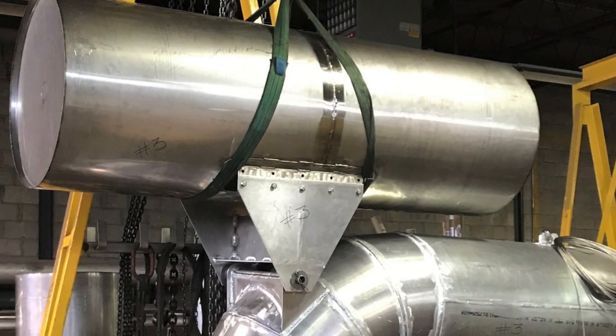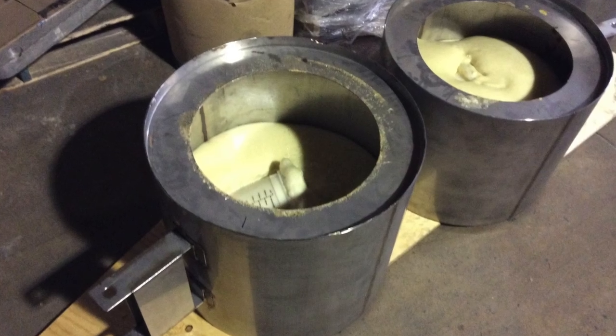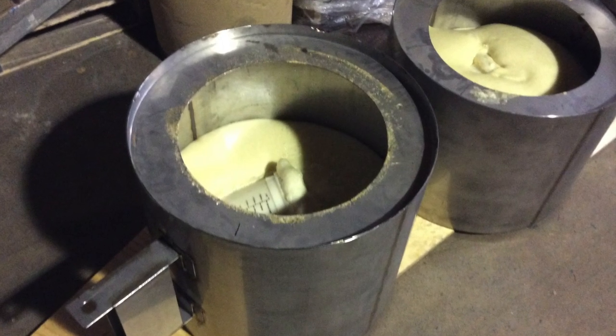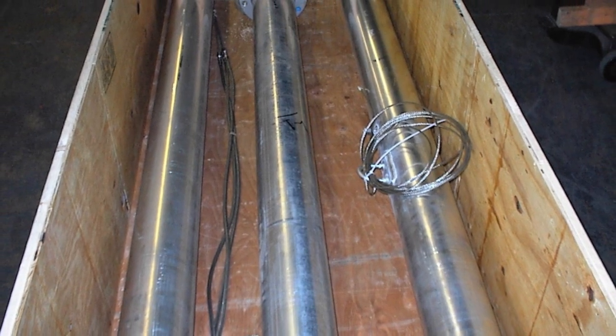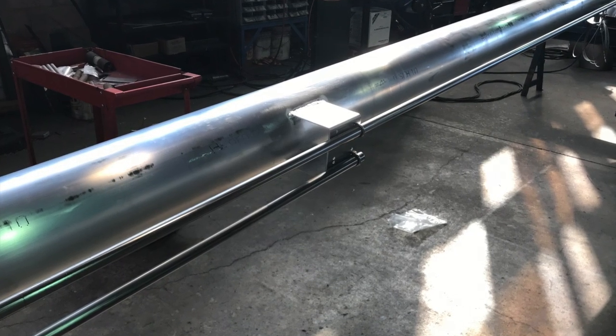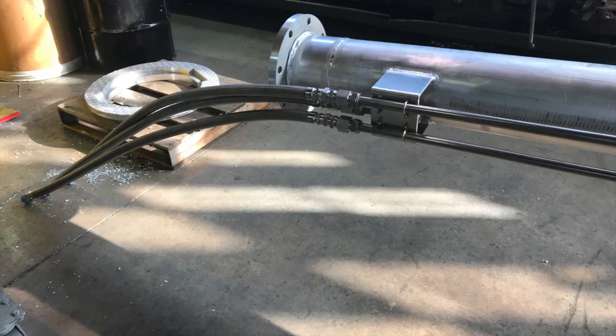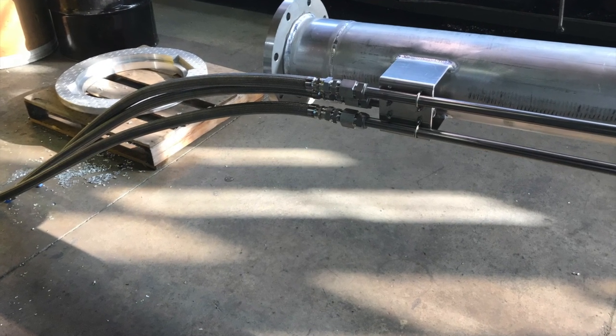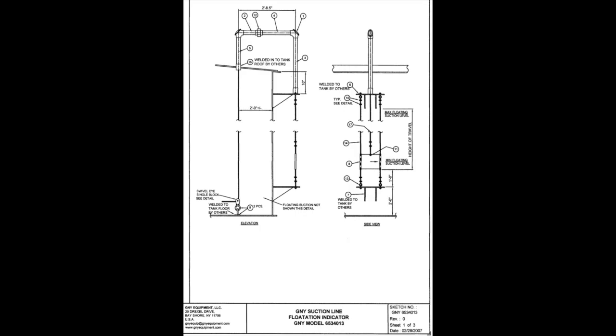The stainless steel floats are designed with separate compartments and are all pressure tested. Unsinkable foam-filled float assemblies are available. The uncoated stainless steel inspection cable is standard, and tethered cable is included in the assembly. Accessories available to fit particular installations include a 3-point sampling system, chain or roller assembly for floating roof, and level indicators showing arm position from outside the tank.